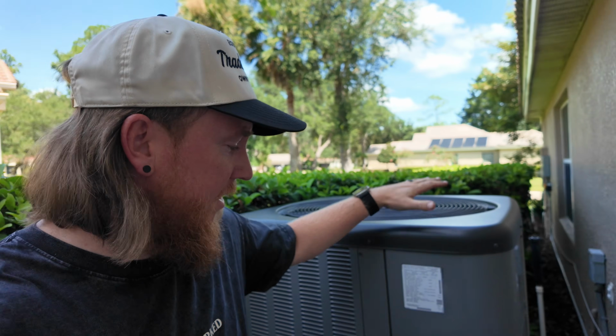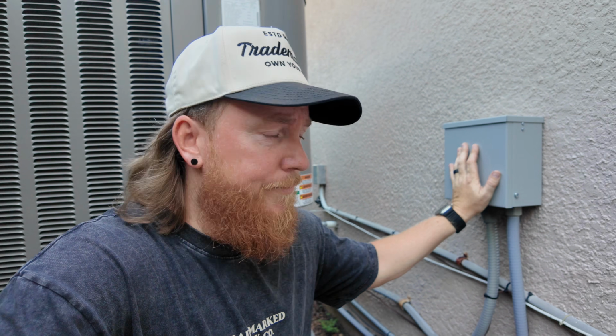This is actually one of those 18-SEER communicating systems. And when we installed this system, I went ahead and put the ICM 493 in here. This is a voltage monitoring and surge protector. What they're having an issue with is the system's losing communication between the condenser and the air handler. So I'm gonna go ahead and inspect this, see if this is giving me any faults, because there are no alerts inside. And what the customer's having to do is reset the breaker because of the communication from this inverter board. So I'm gonna open this up and take a look and see what's going on.